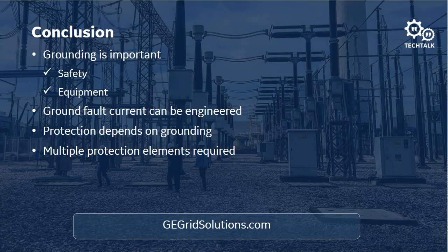So the third question we'll take is, does high impedance grounding have a practical significance at industrial facilities? Based on our discussions, I would think yes. It provides the maximum service continuity. We don't have to stop the process immediately; we could take the process down whenever we need to. We can keep the process up because we're not subjecting the machine to large amounts of fault current. There's basically no ground fault current being introduced.